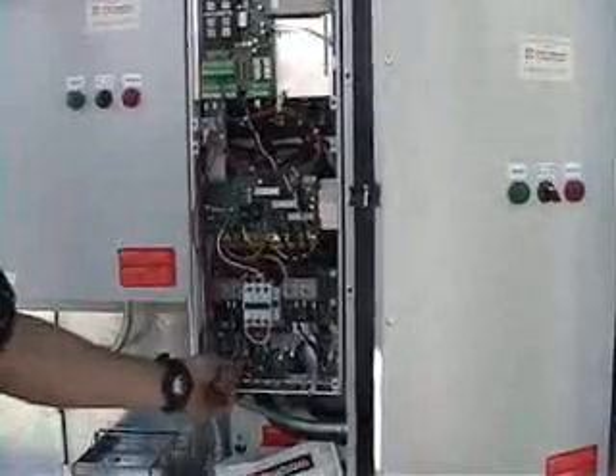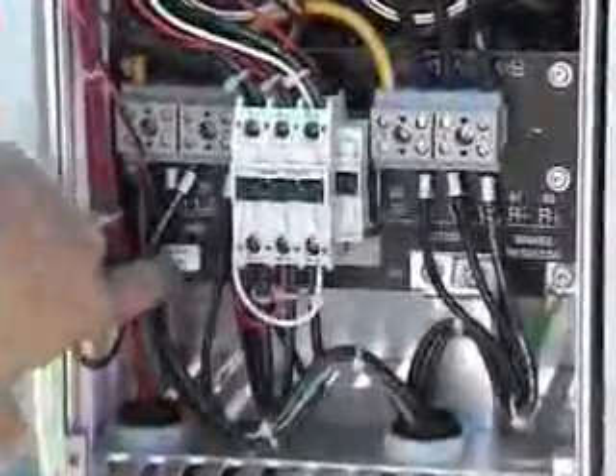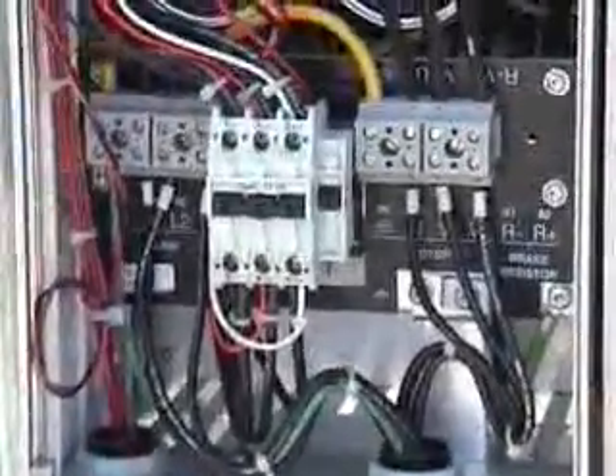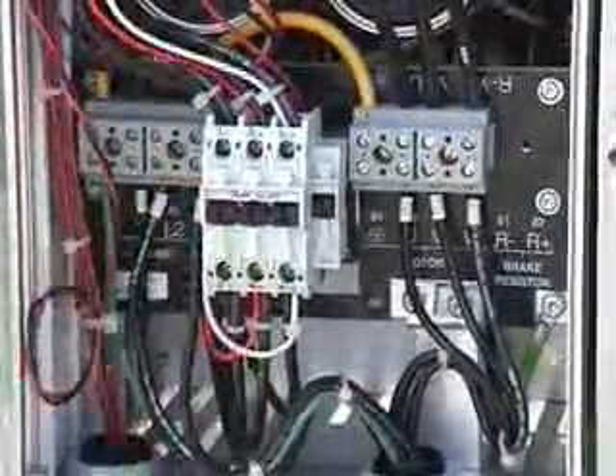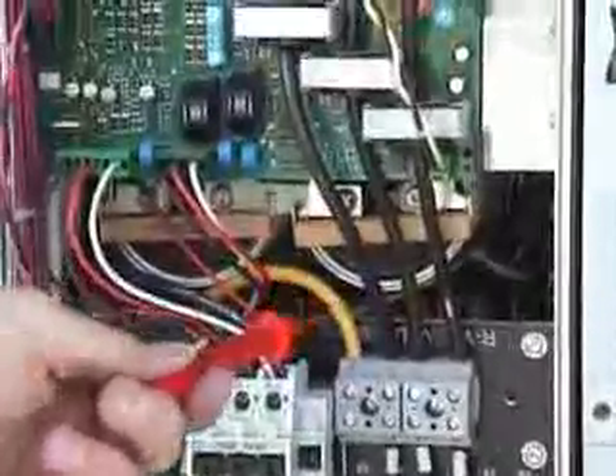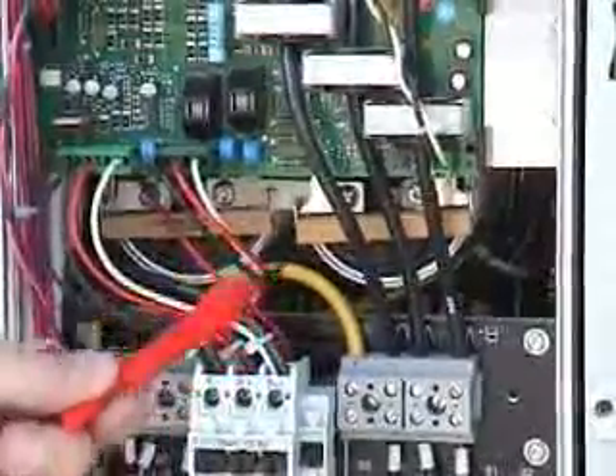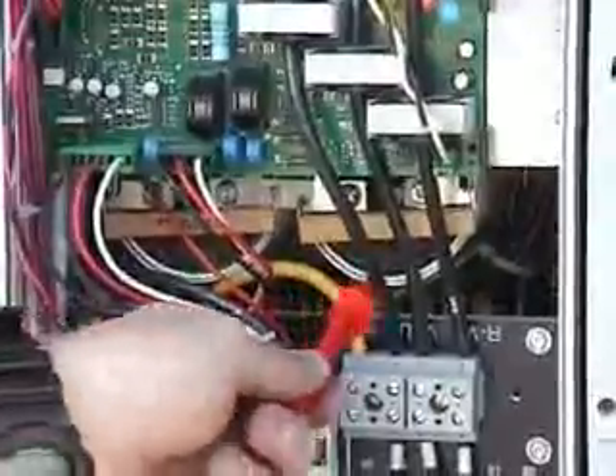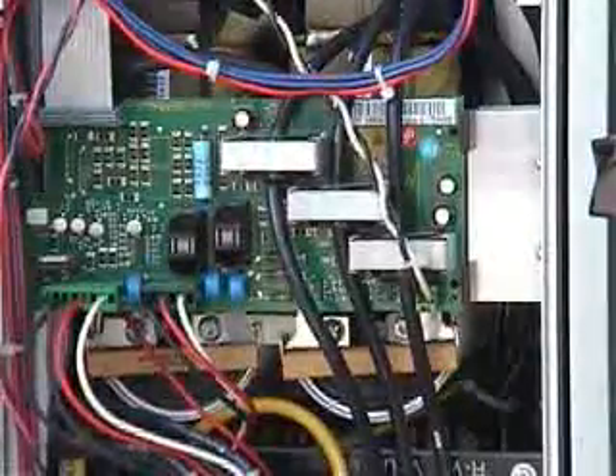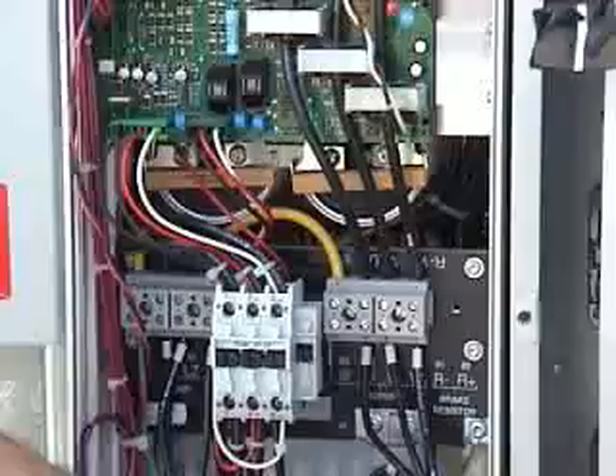This is where our power is coming into our VFD right here. If you look right here, it says line, so that's our input. So we come in here, we go through the controls, but there are some things to point out in here that are kind of interesting. You'll notice back in the back, these round things, those are two giant capacitors, a little bigger than we use in lab. These beige colored devices are actually giant resistors across those capacitors. So you have a really big RC circuit right here. These little devices right here are current measuring devices. They actually measure the current that we're putting out to the motor.